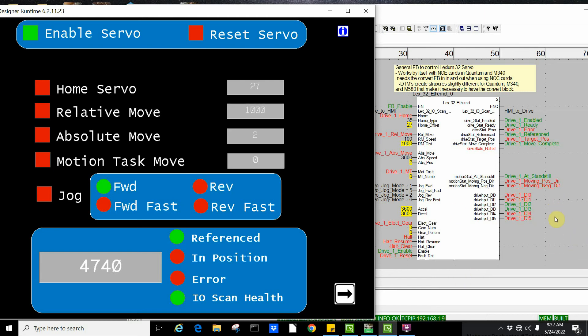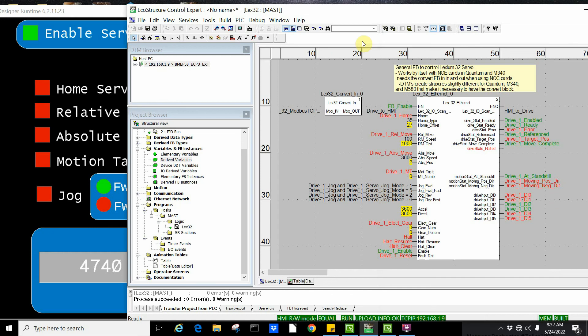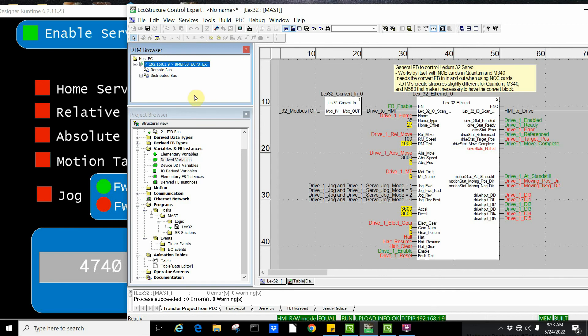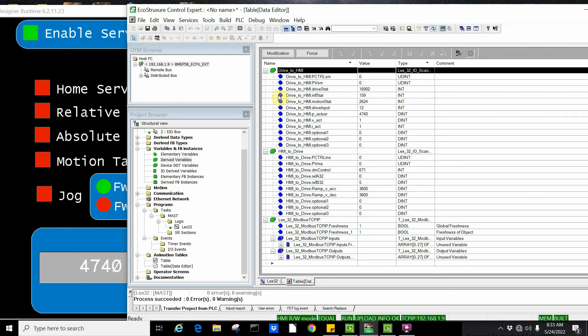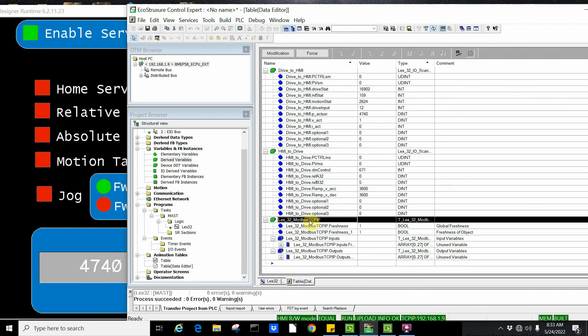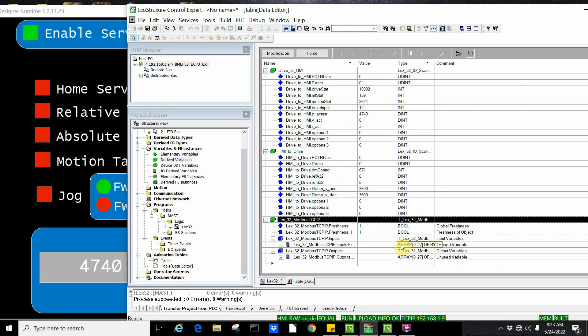Looking at this function block, when I set this up, this variable because I did 13 words in and 13 words out, I actually made a little table here. Here's the variable that was created when I made that DTM. Here's where I get the health of the transaction going to the drive and animation table. Because the M580 is a double word processor, even though I asked for 13 words, it actually gives me 28 bytes or 14 words because it has to pad it to be an even number of words coming out.